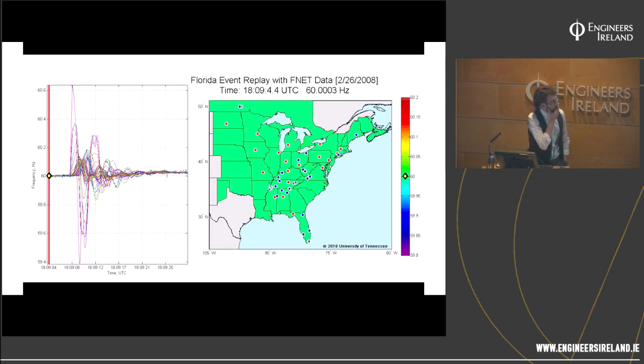So this happened back in 2008. So I suppose the things I want you to look out for is there's a fault on the system in Florida. The frequency rises. Because of this lean blowout, the gas turbines disconnect. So all of a sudden we have a generation consumption imbalance. The frequency falls. And you'll see the results in the network frequencies all around the US grid.